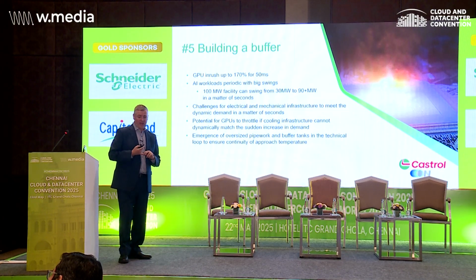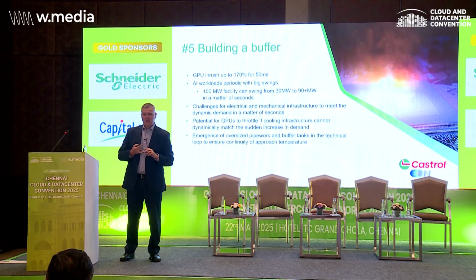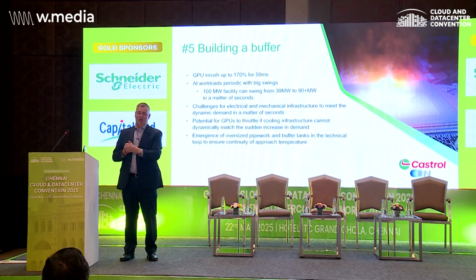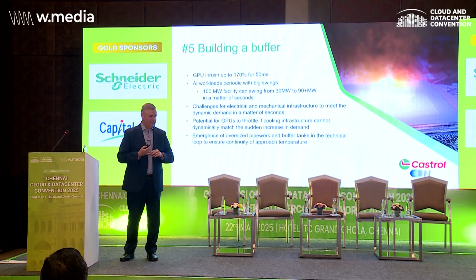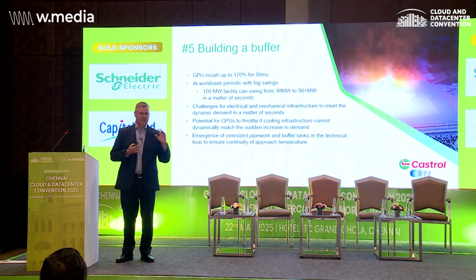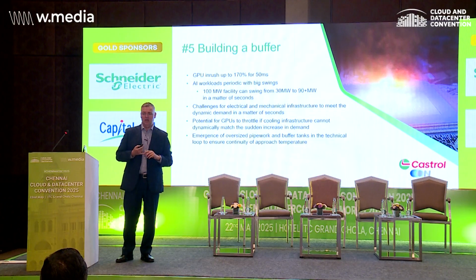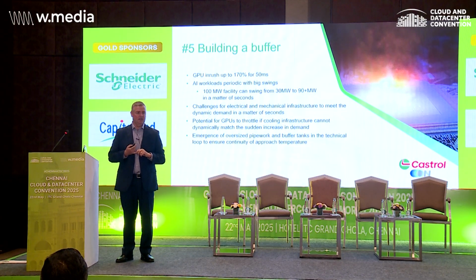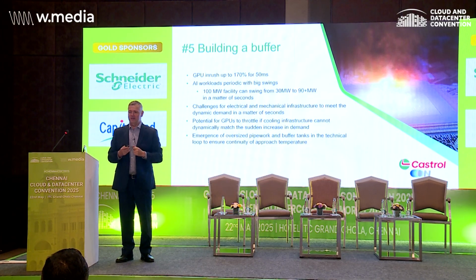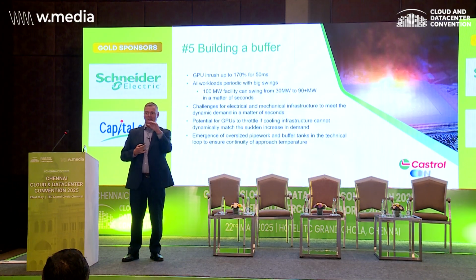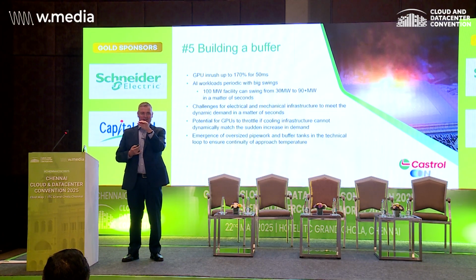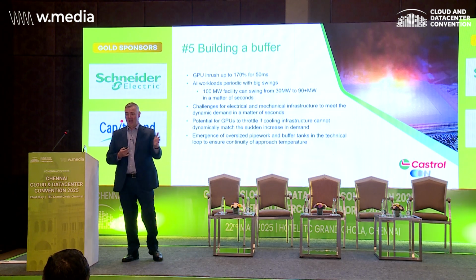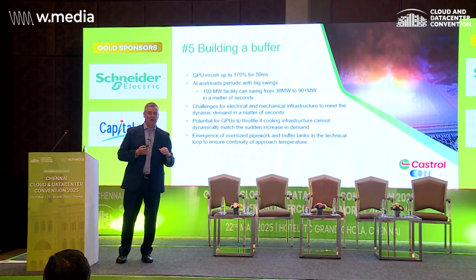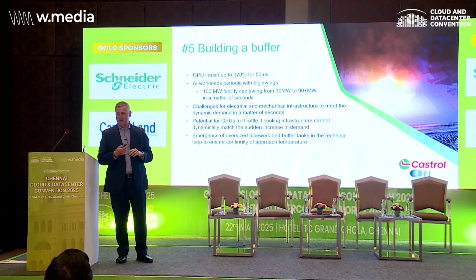With AI workloads, this is probably the most important piece: they have big swings. A gentleman from Oracle I did a presentation with told me a typical AI workload might run for 5 minutes at 90%, then drop down and rest for a minute, then kick back up to 90% for 5 minutes, then drop back down to 30% for a minute. Let's build that out to a 100 megawatt data center: 30 megawatt, 90 megawatt, 30 megawatt, 90 megawatt. I feel sorry for the power guys, like how the energy provider is going to deal with that on the power side - that's difficult enough.